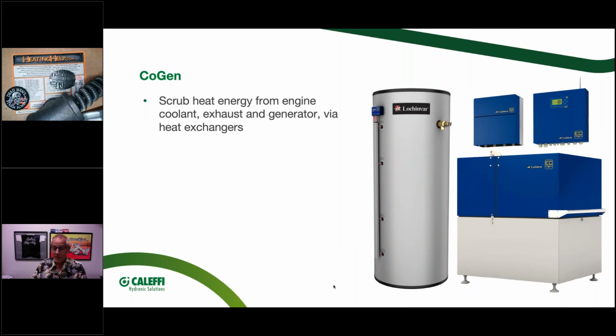Cogen - if you ever get a chance to look under the hood of a really nicely engineered cogen unit, like this one Lochinvar is bringing in from the Scandinavian countries, I think, for them - if you take the jacket off and look inside, there are heat exchangers everywhere. They're using the coolant water from the diesel engine to pull the temperature and put it in the buffer tank. They've got one on the exhaust manifold too.